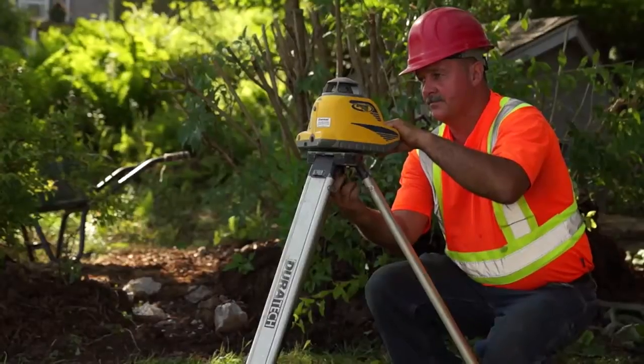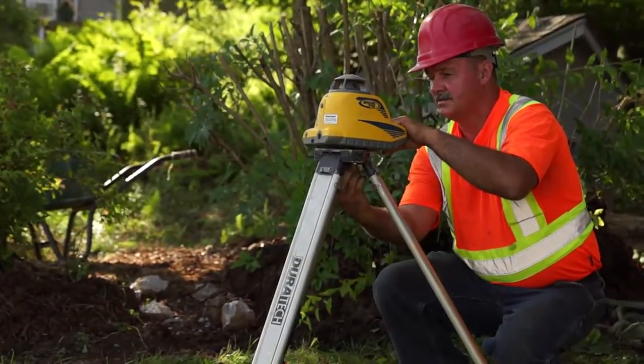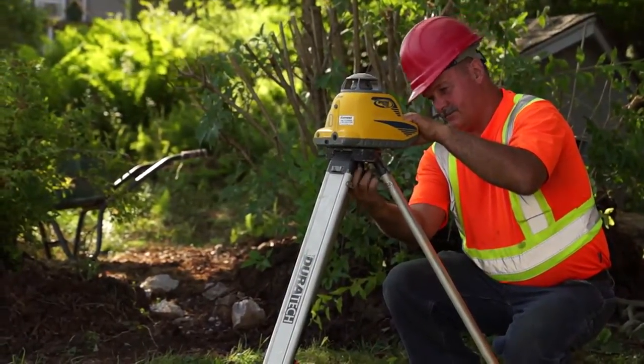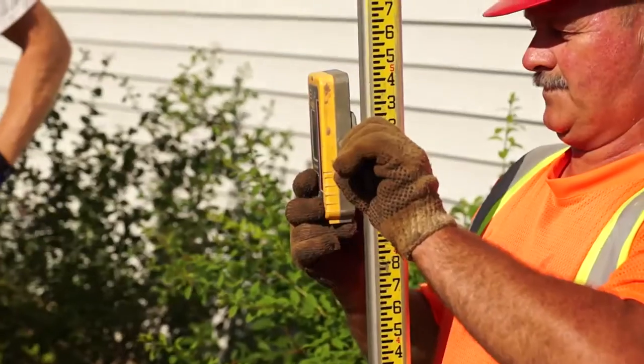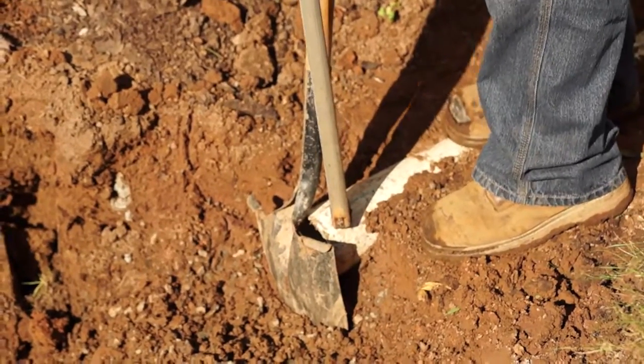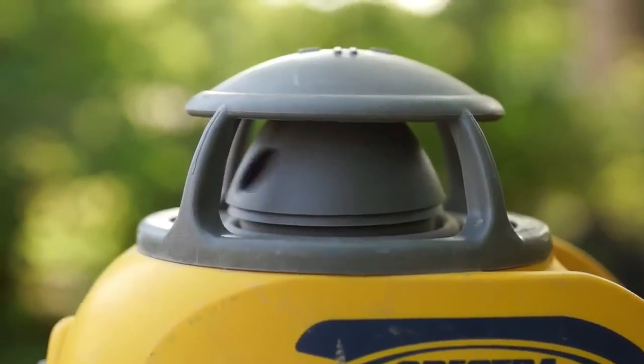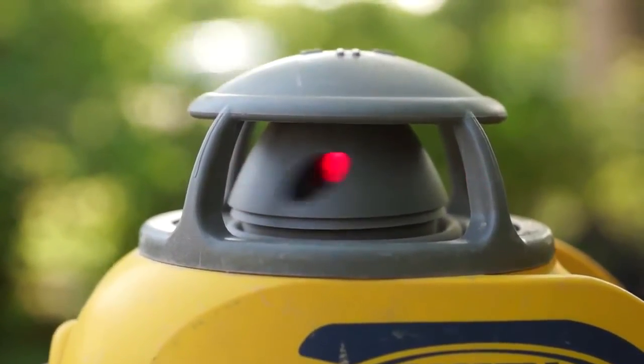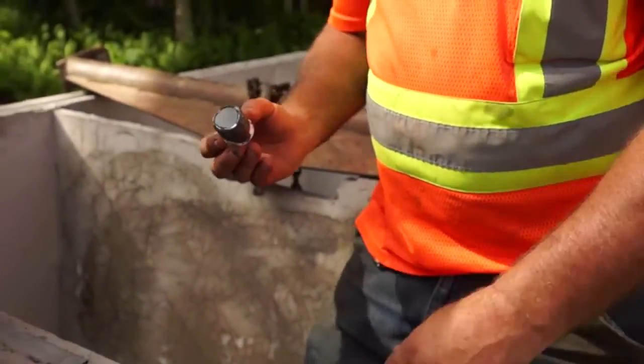The site is excavated to the proper depth and raked level, allowing for a minimum of 2% slope on the pipe from the house to the tank and a minimum of 1% slope from the tank to the bed. If a drain hole is present in the bottom of the tank, a plug must be glued into place.